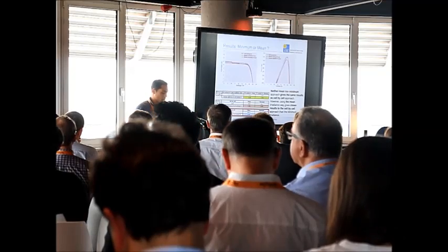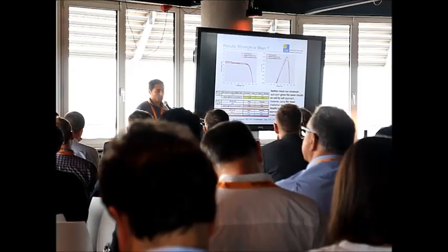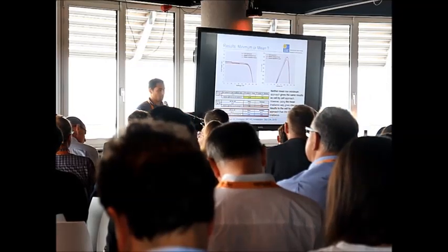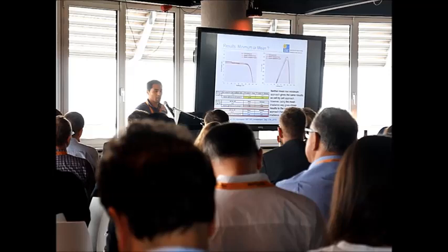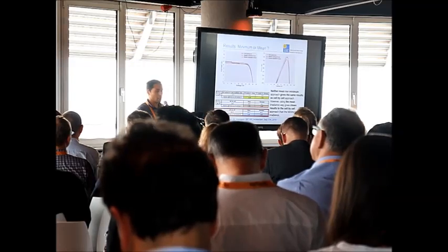Looking numerically, especially at power, we found that the mean value overestimates a little bit, by 1.2% compared to the cell-resolved IV, while using the minimum irradiance on the backside leads to a very high underestimation of 3.6%. So in conclusion, neither the mean nor the minimum approach gives the same result as the cell-by-cell method. However, using the mean value on the backside leads to results similar to the cell-by-cell method.